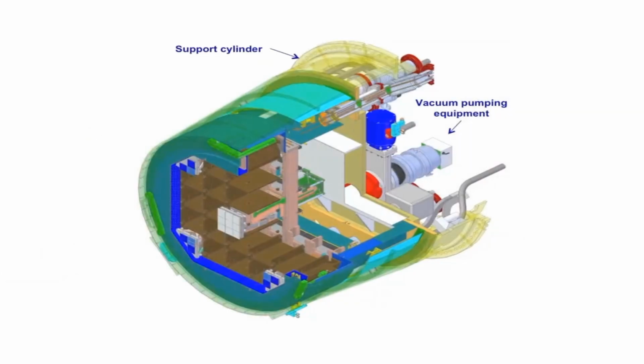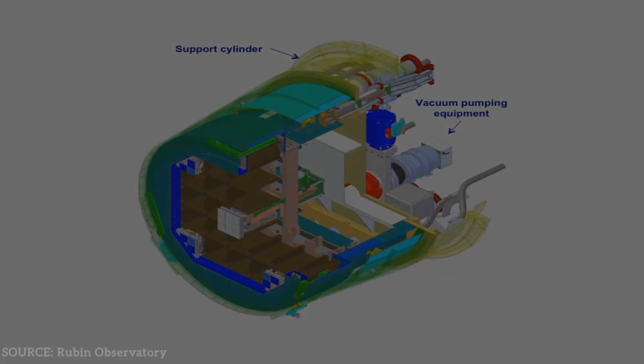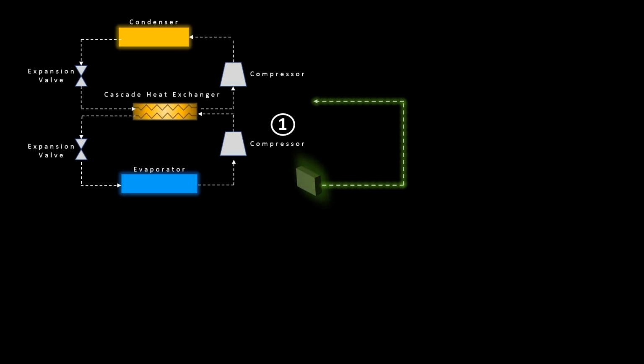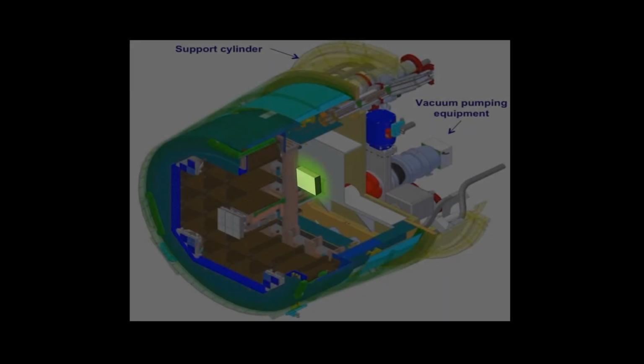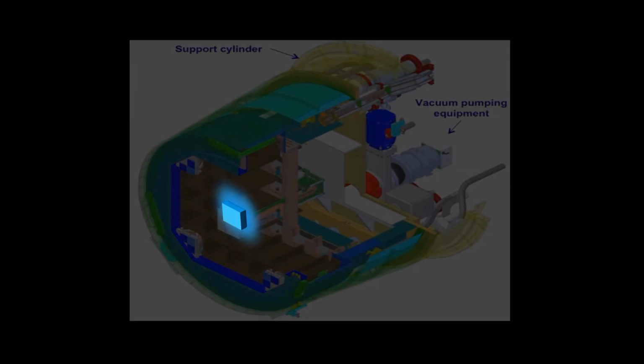The first cooling system inside the assembly chills the analog to digital electronics using a 2-stage cascade refrigeration system, wherein, instead of 1, 2 cascade cycles cool the target down to minus 40 degrees Celsius. But the real magic happens deep inside the cryostat, where the camera's ultra-sensitive eyes, the charge-coupled devices, are cooled to a bone-chilling minus 130 degrees Celsius. This extreme cooling is achieved using an advanced auto-cascade refrigeration system.